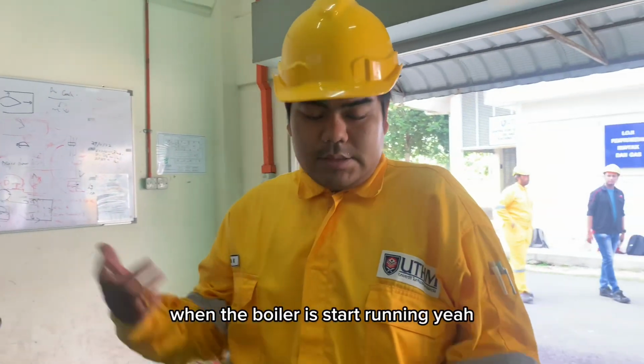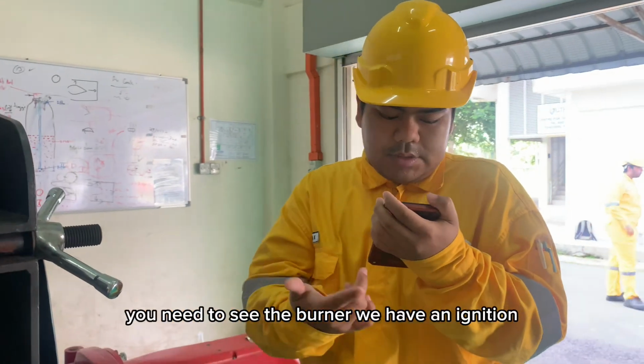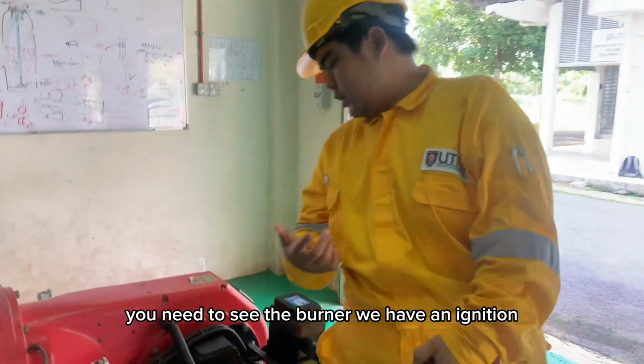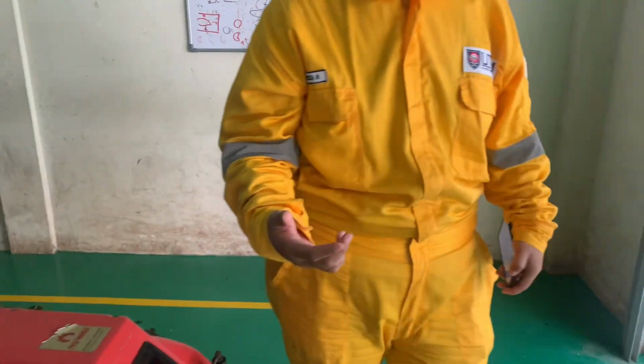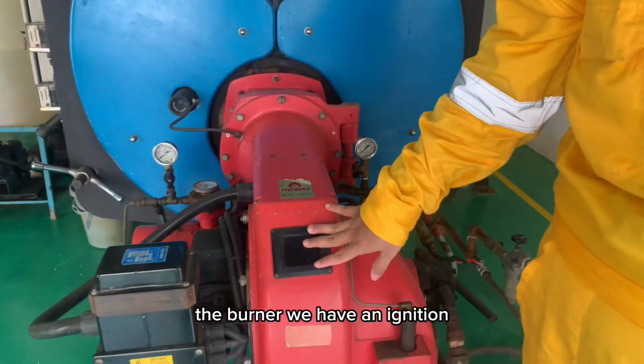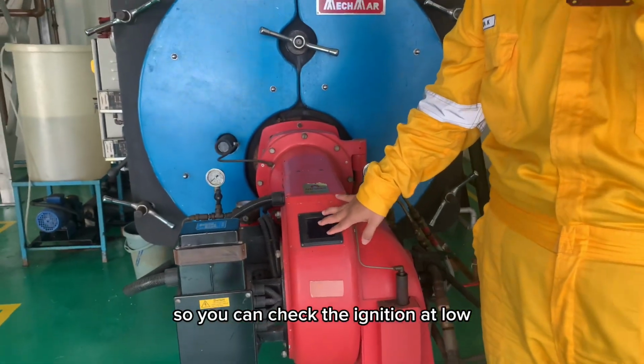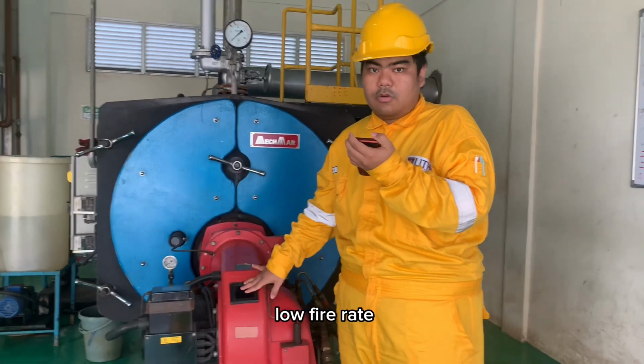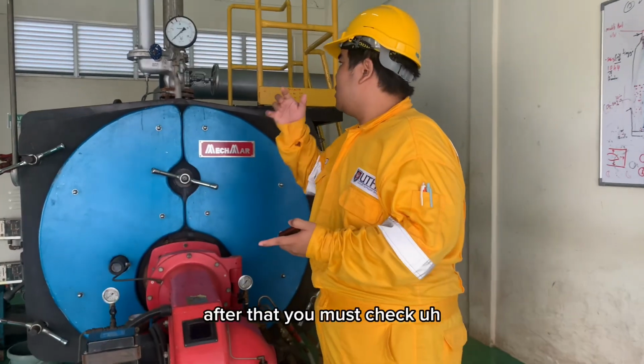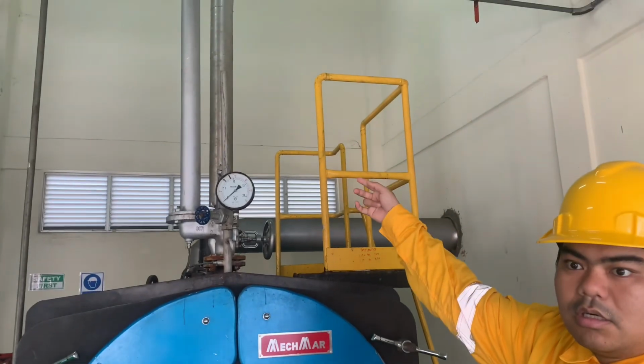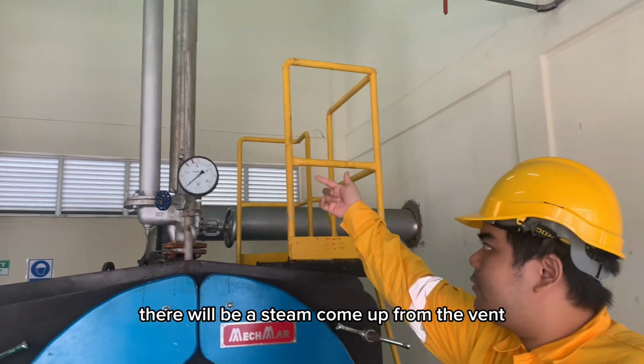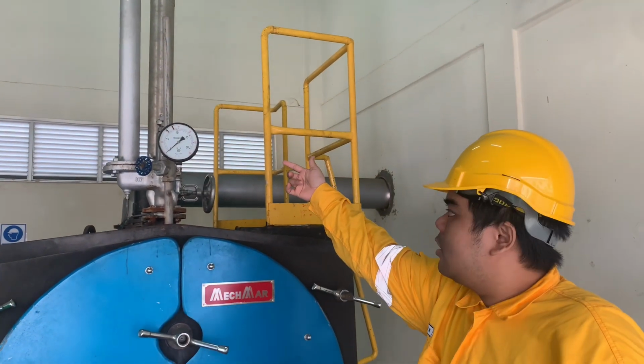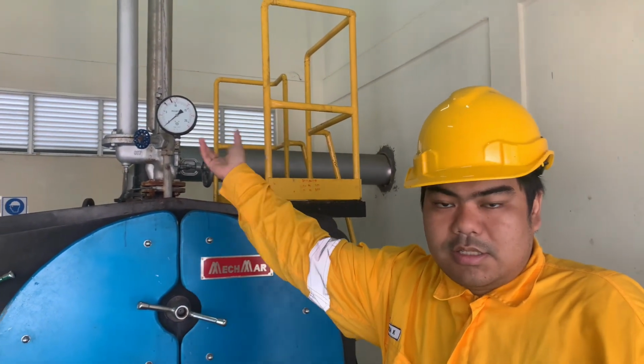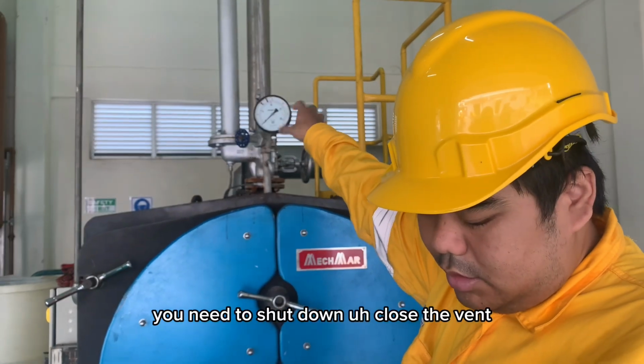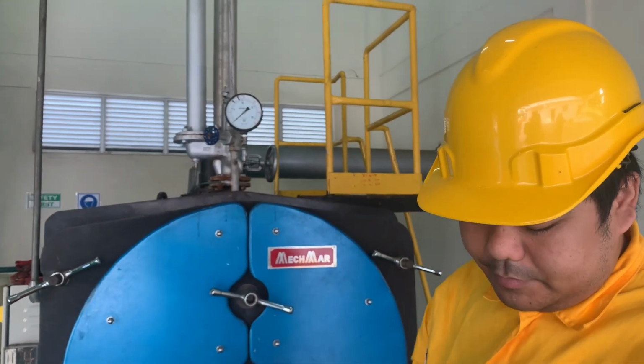When the boiler has started running, you need to see that the burner has ignition. The burner will have an ignition, so you can check the ignition at low fire rate. After that, you must check. There will be steam coming out from the air vent. Then after that, you need to shut down, close the air vent.